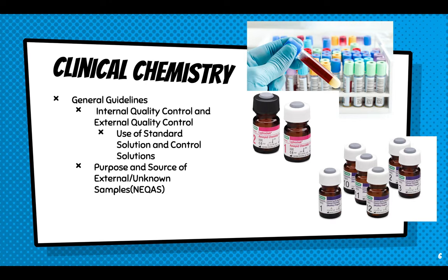Going back now, we will also be discussing the use of standard solutions and control solutions. If you can still remember, we described your standard solution as the same as your calibrator and your calibration standard. So all are the same. Aside from that, you will also be doing your control solution. We discuss the ideal characteristics of your quality control material. At the end, before we proceed to other parts of our discussion for this morning, I will also be showing you some videos so that you will have a better understanding of how it is being done in the laboratory.